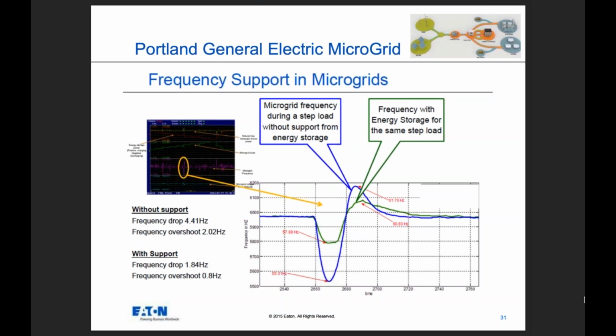That's what happens without the generating capacity that used to exist. Again, shutting down the coal plants, retiring nuclear plants, we just don't have these big rotating generators spinning with all that iron, mass, and weight behind them. So when that frequency slows down, it's damaging the existing generators. It really doesn't impact the customer a whole lot. It would mean if you had a clock running off that frequency, the clock's going to run a little slower, but you'd probably never notice it.